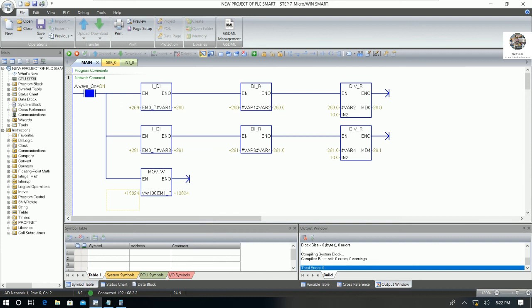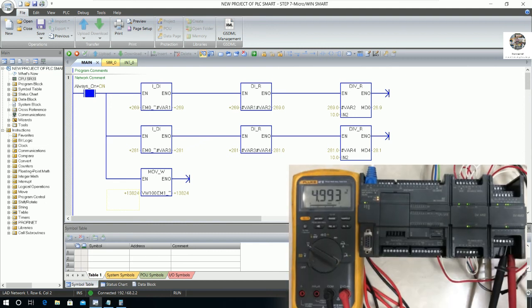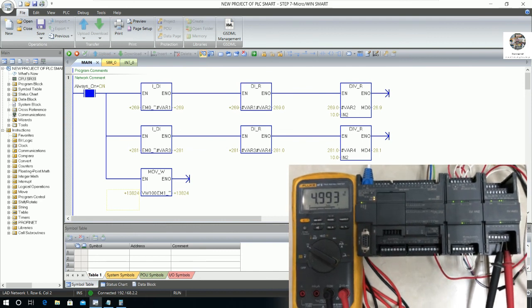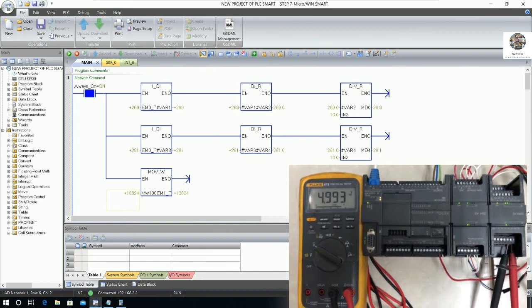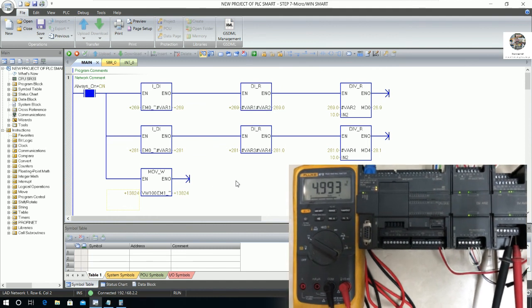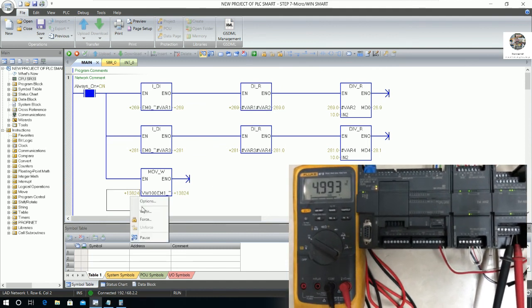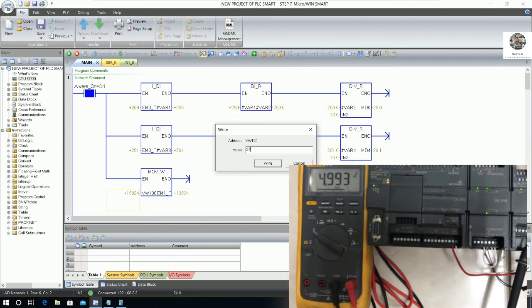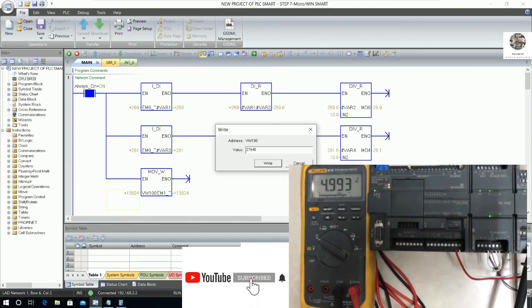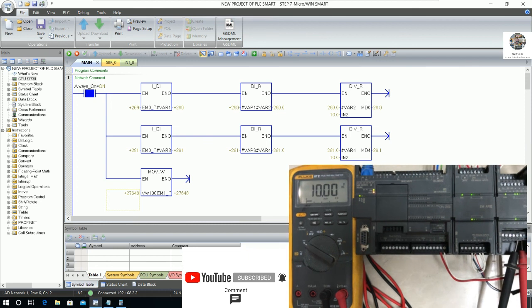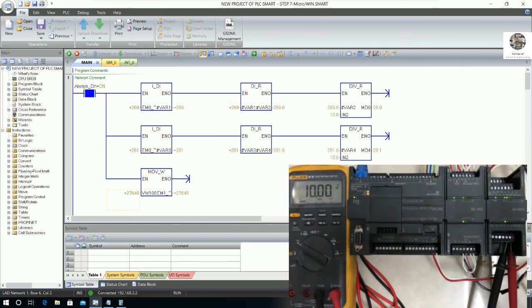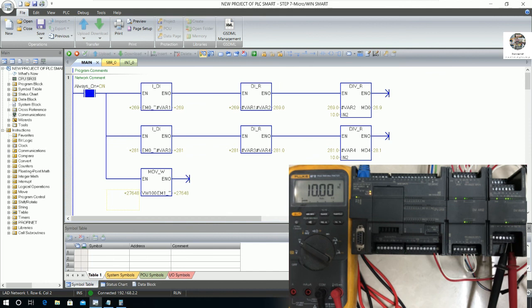Let me show the multimeter reading — it shows around 4.99 volts. If we want to set the maximum output, set the value to 27,648 and we get 10 volts. This demonstrates the analog output working correctly.